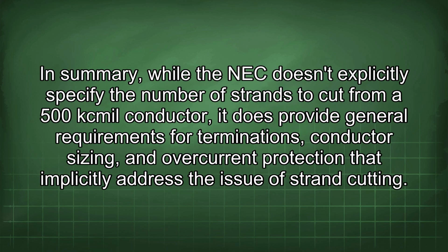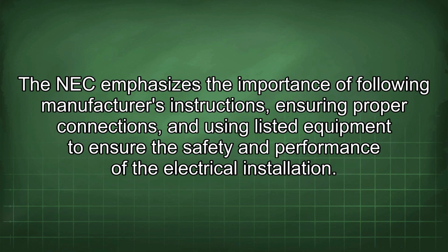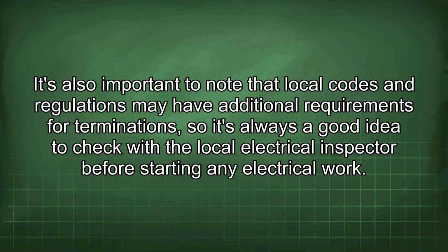In summary, while the NEC doesn't explicitly specify the number of strands to cut from a 500 kcmil conductor, it does provide general requirements for terminations, conductor sizing, and overcurrent protection that implicitly address the issue of strand cutting. The NEC emphasizes the importance of following manufacturer's instructions, ensuring proper connections, and using listed equipment to ensure the safety and performance of the electrical installation. It's also important to note that local codes and regulations may have additional requirements for terminations, so it's always a good idea to check with the local electrical inspector before starting any electrical work.